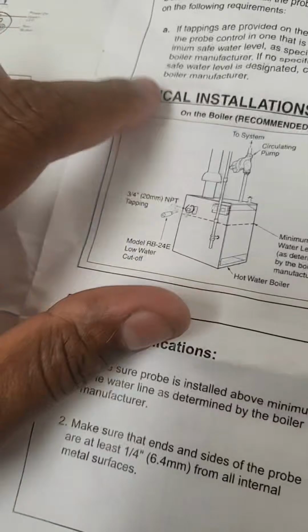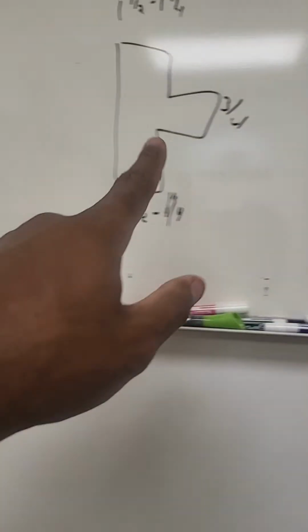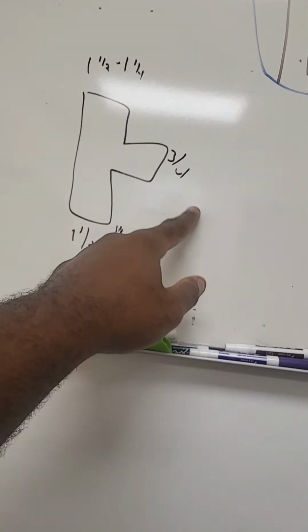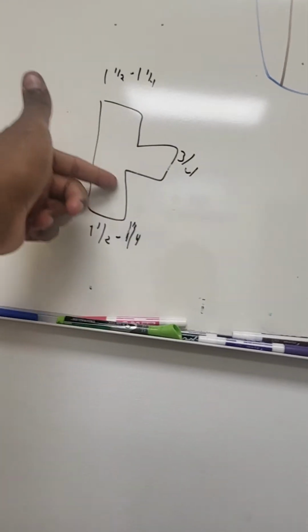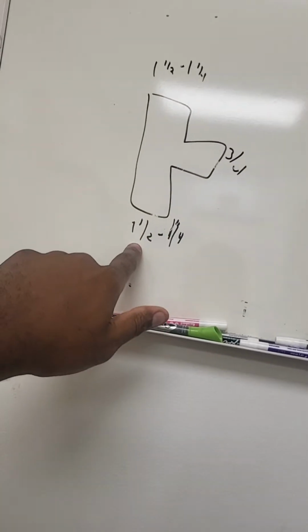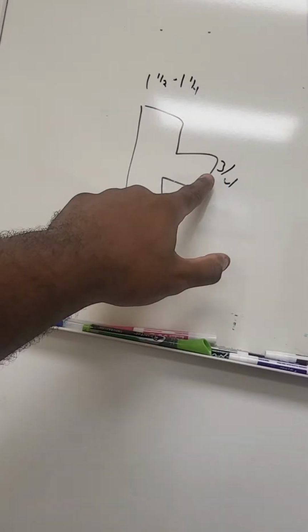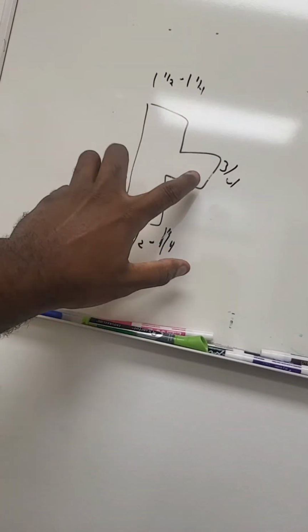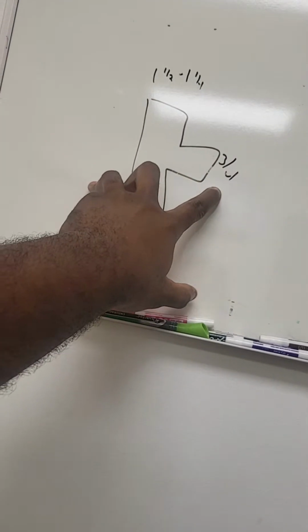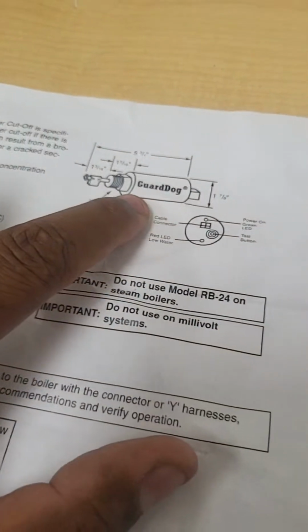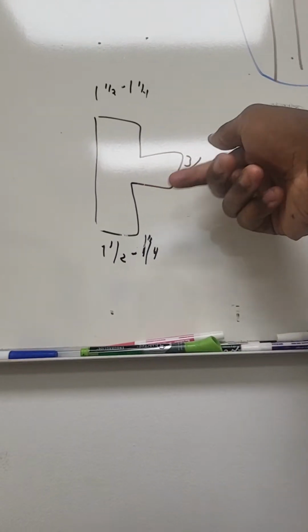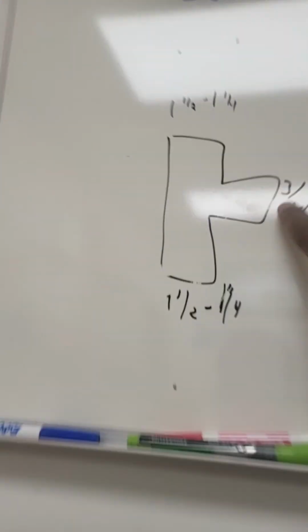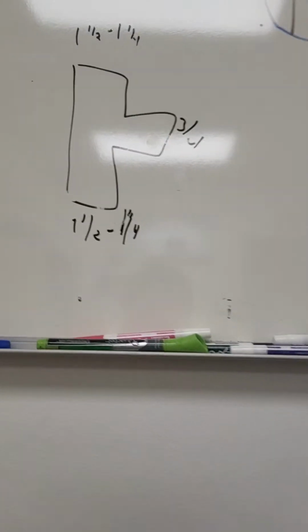Here's the thing, guys, real quick. If you already have this tapping on the boiler, you just drain it down. This is nothing more than a black T, a 1.5 inch or 1.25 inch by 3/4 inch T. The middle part, the 3/4 inch, is what goes into this. But there's no well, so if you don't listen and try to unscrew this low water cutoff, you're going to get blasted and flood the house.